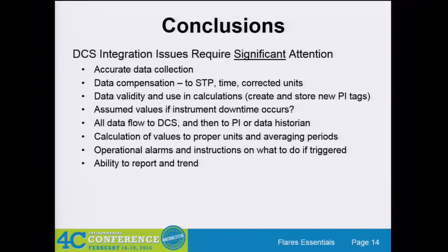One other thing to think about is, once you do all this stuff, you also have to think about your alarms. When do you need to tell the operator that the automatic system is not going to work? We need you to do something. That's a whole other set of logic to be able to tell the operator, hey, pay attention to me. I need you to adjust something.